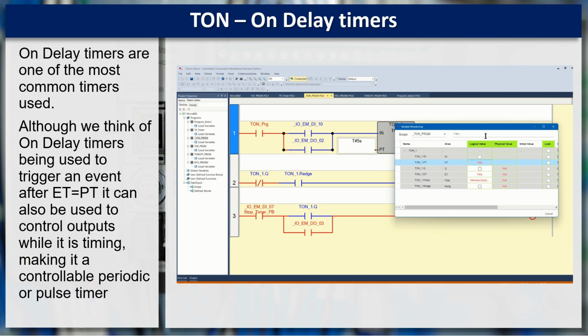This whole portion would not be counted towards the total time. So by looking for that trigger, that rising edge, it's saying the second you see that, that's when your timing starts. And if it happens to miss it during a scan, it knows the last scan and it can actually timestamp it and look back and go, okay, I've got to add that to the time.